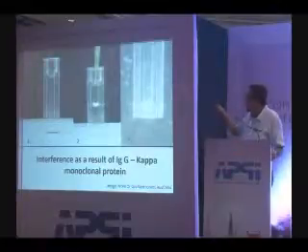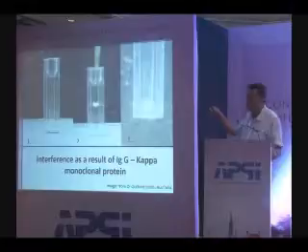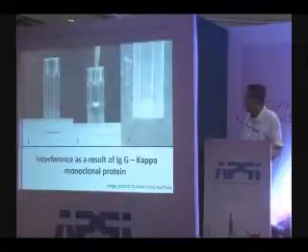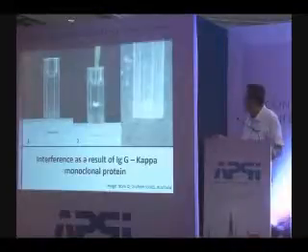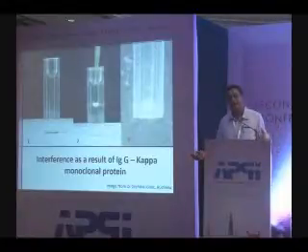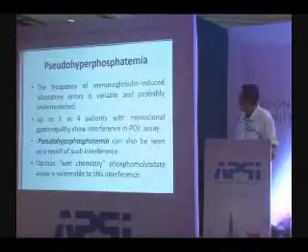Now, here is what happens inside an autoanalyzer. The first is just the phosphomolybdate reagent in a cuvette. What happens when we add an IgG kappa sample to it? You can see the white precipitate being formed here. And it's enlarged; this is the large precipitate which is formed. It forms in a flash of a second. The analyzer reads it as an absorbance spike and gives you incorrect phosphate results.